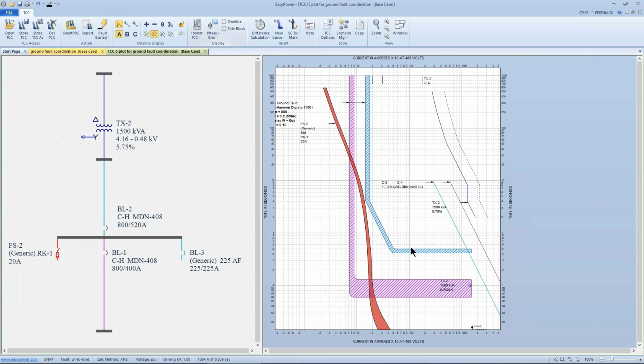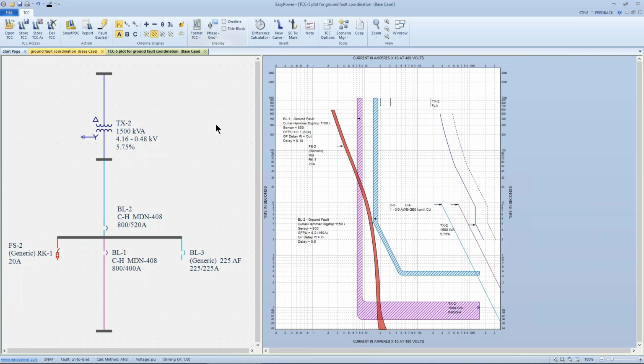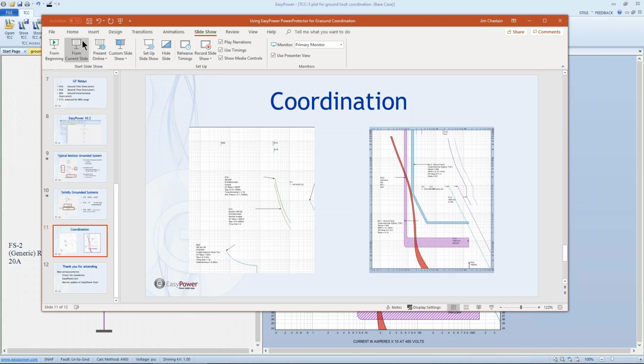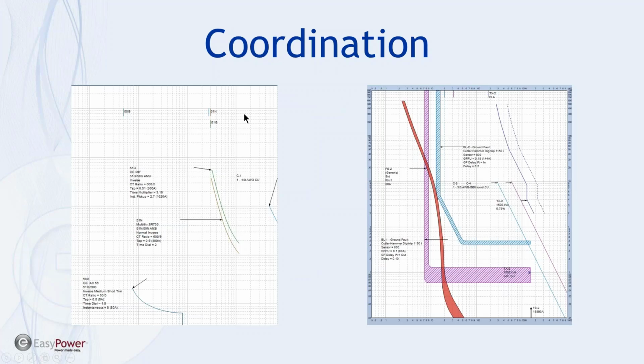So at that point, and this can be adjusted if we want a little bit better separation or less, we can make these adjustments on the screen or in the setup of the breaker itself. So at this point, it looks like we have fairly good ground fault coordination between the upstream main, the downstream, and at least one of the feeder fuses. And we'd save this plot and call it good. All right, so that was kind of the short and sweet version of it.